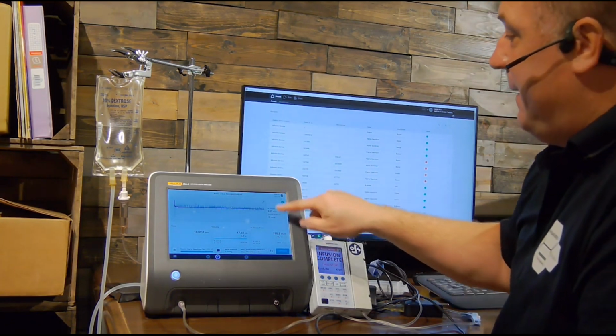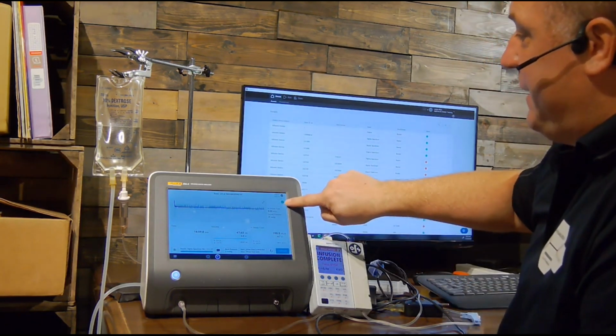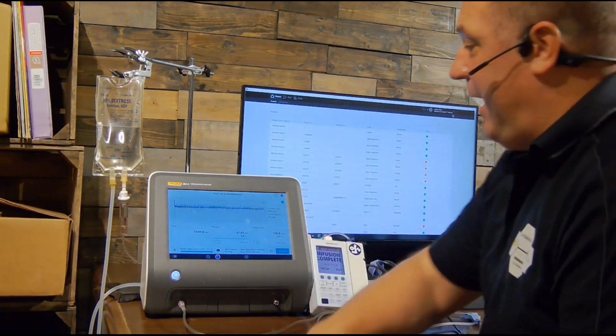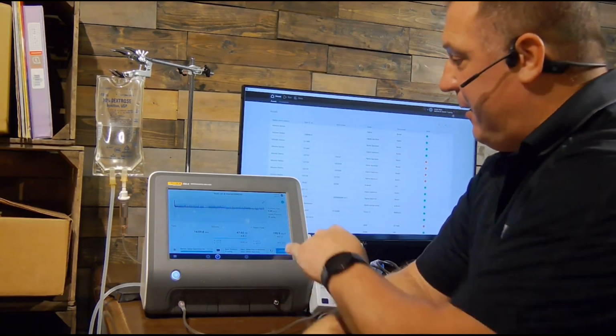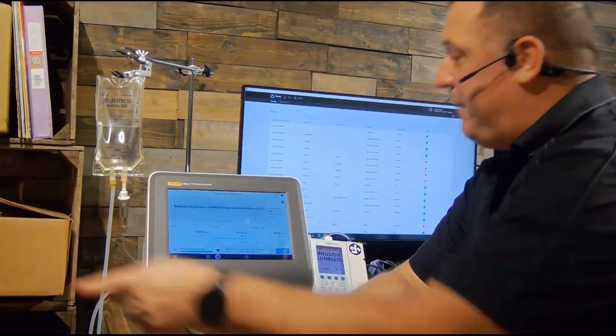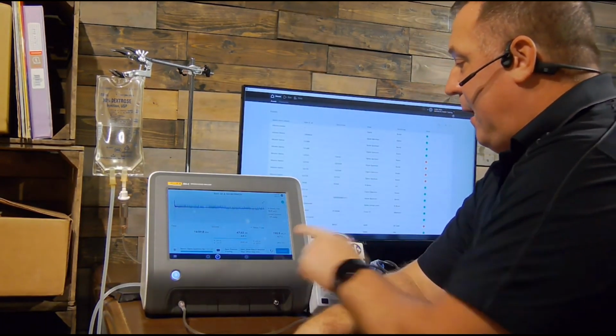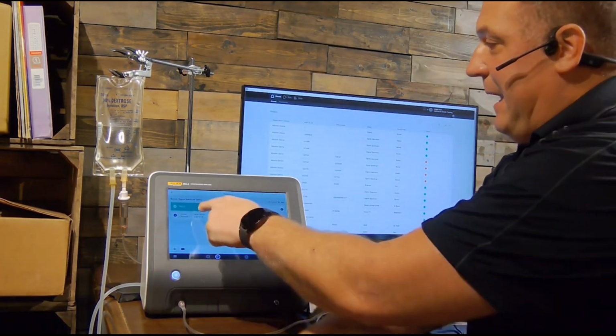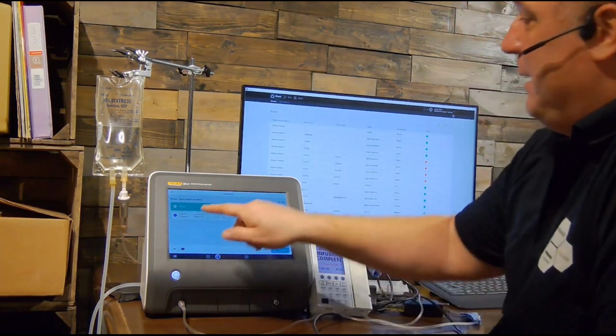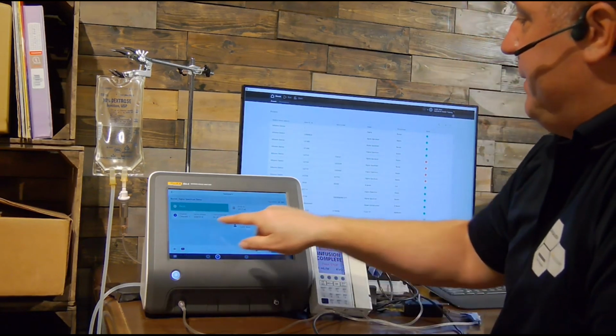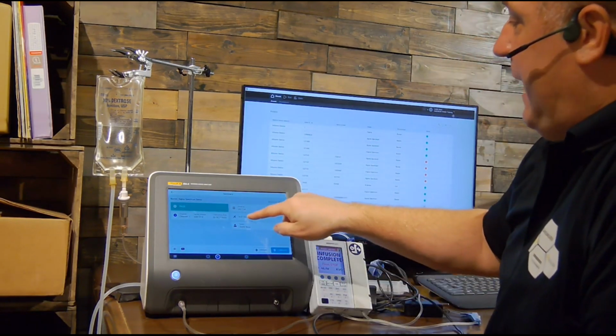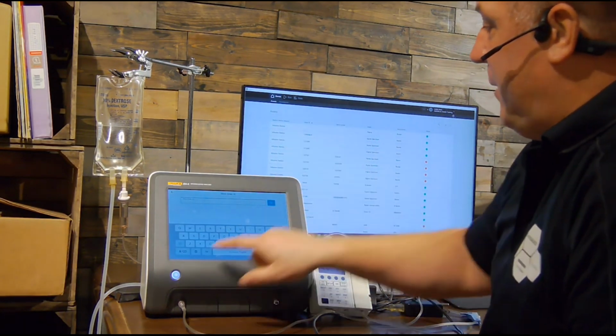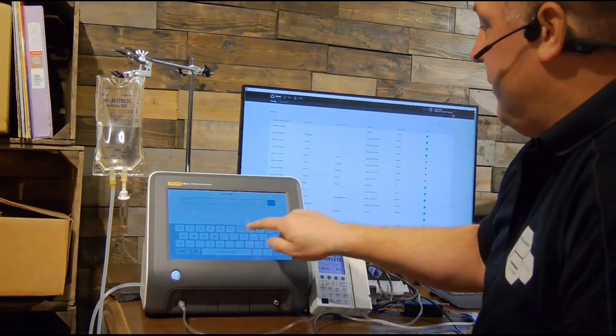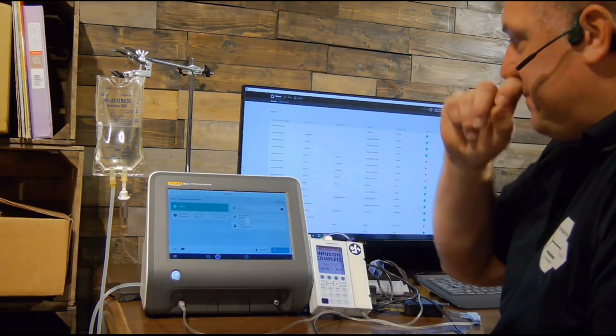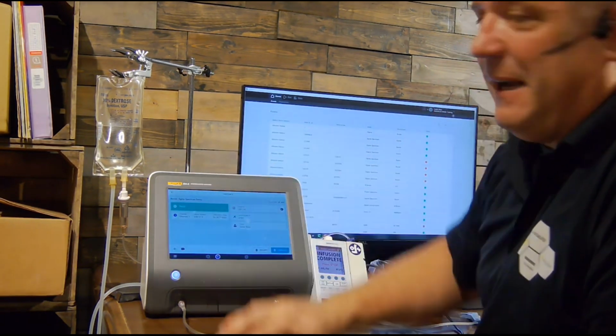So this step passed, and I have a green light here. Now that that's done, if it had failed, I could push this circle button here and go back and redo the test. But it passed. I'm going to push continue here. And I got a passing score here. So here's all my information for the pump, my asset ID. If I had my work order ID, I could type it in here for my work order, or we'll just make a number up there. Here we go. Everything I need to know is here.